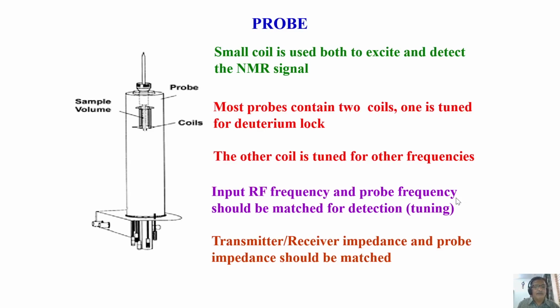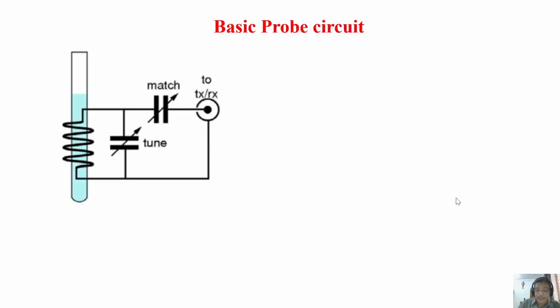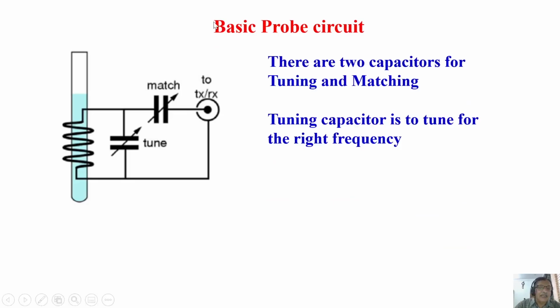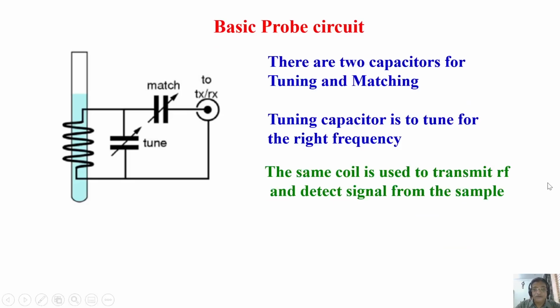And also you have to ensure that the impedance of this transmitter and receiver is matched so that maximum power of what you put in goes to the sample, and there is minimum reflected power. That is called matching. So basically this is a probe circuit. It is nothing but a simple LC circuit. There are two capacitors: a tuning capacitor to tune for the right frequency, and a matching capacitor to match the impedance.